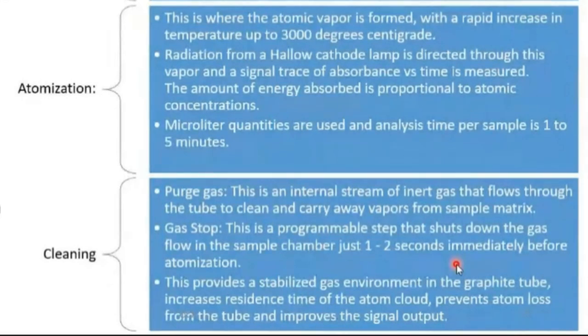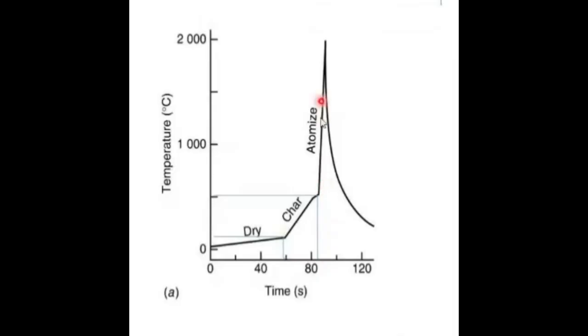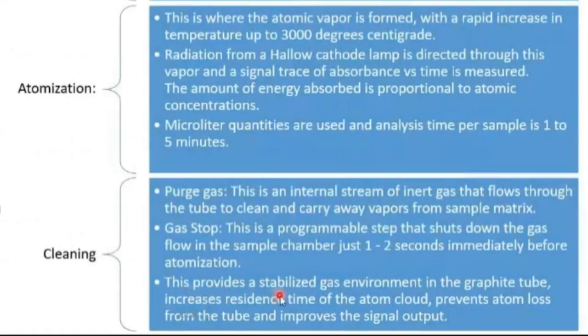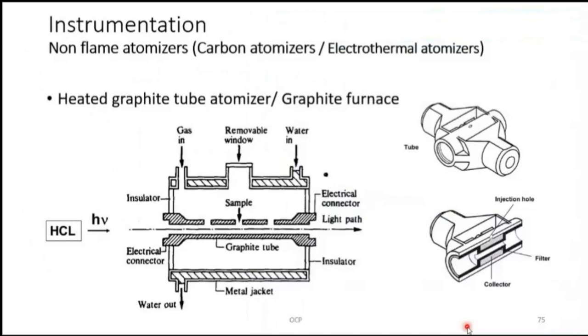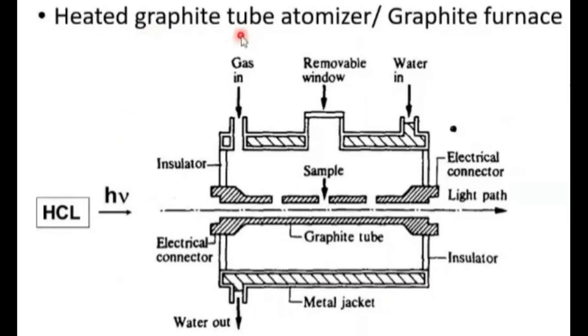There is a continuous flow of gas through the chamber, and for a few seconds the gas is stopped just before atomization begins. This provides a stabilized gas environment in the graphite tube, increases the residence time of the atom cloud, prevents atom loss from the tube, and improves signal output — ensuring atoms remain in the path length for a longer period.